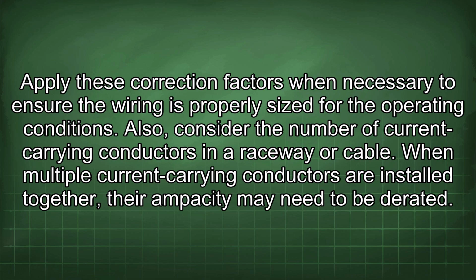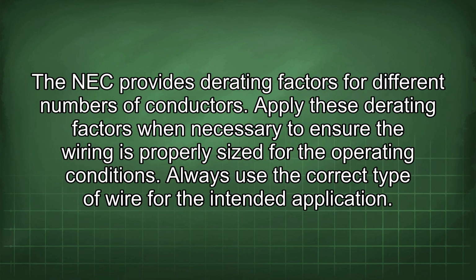Also, consider the number of current-carrying conductors in a raceway or cable. When multiple current-carrying conductors are installed together, their ampacity may need to be derated. The NEC provides derating factors for different numbers of conductors. Apply these derating factors when necessary to ensure the wiring is properly sized for the operating conditions.